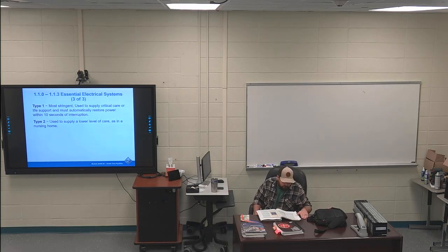On page 4, first sentence, on page 4 in 1.1.1, type 1 is highlighted. Type 1 EES is required in any facility with a critical care unit or that admits patients requiring electrical life support equipment. That's in type 1.